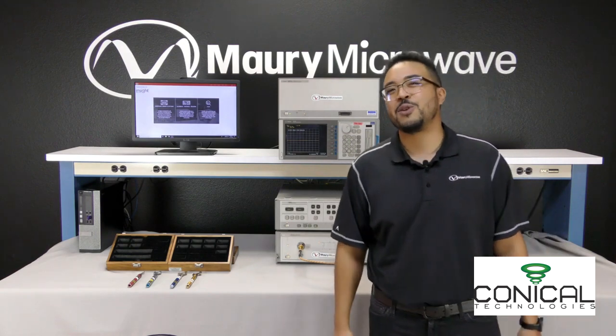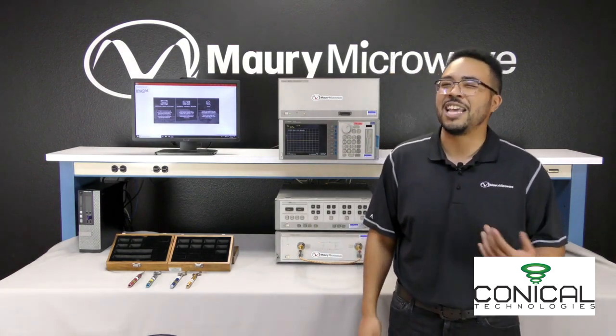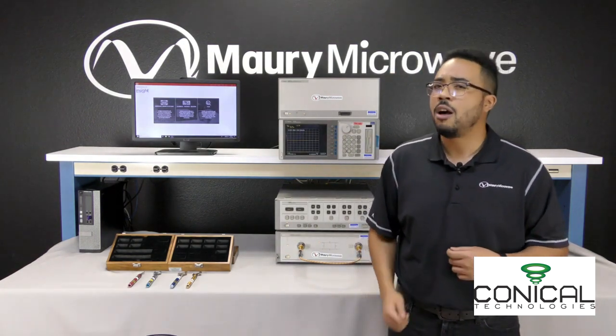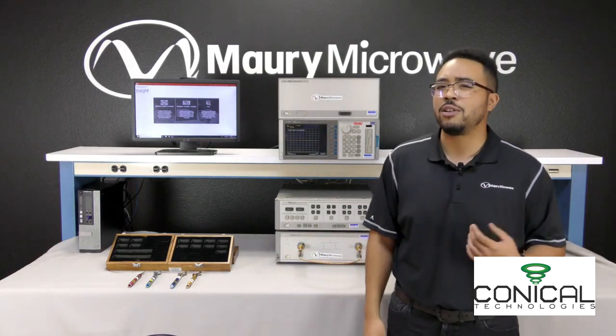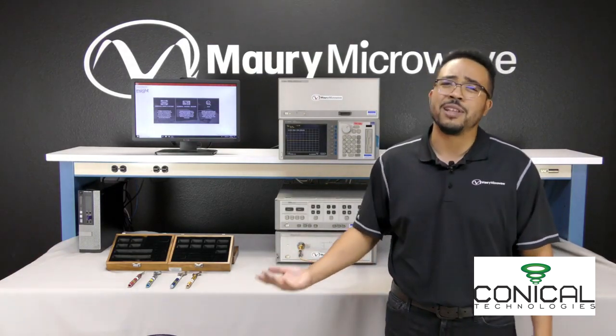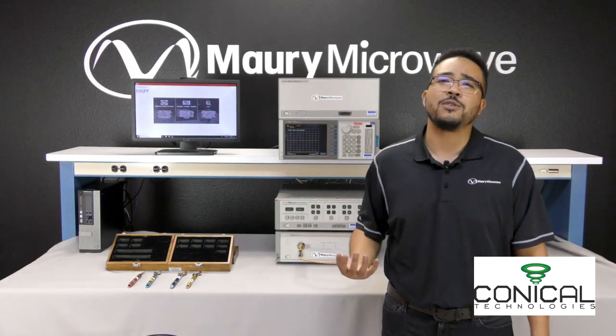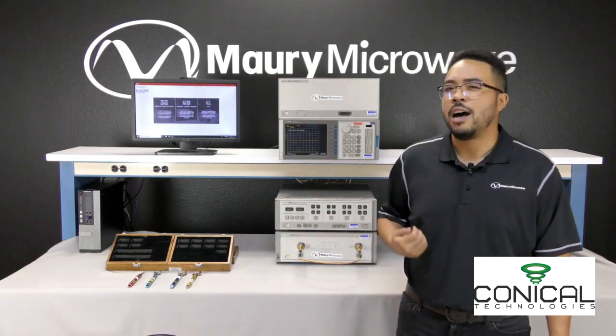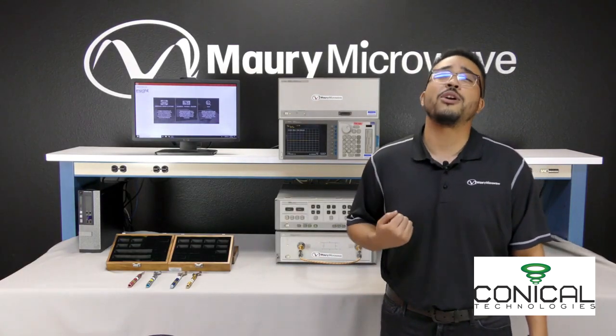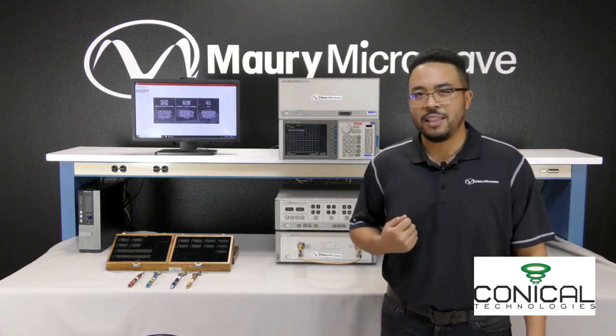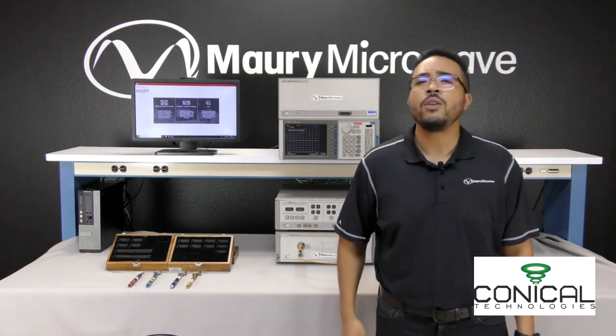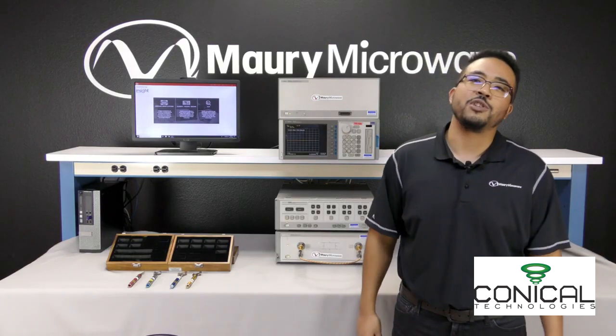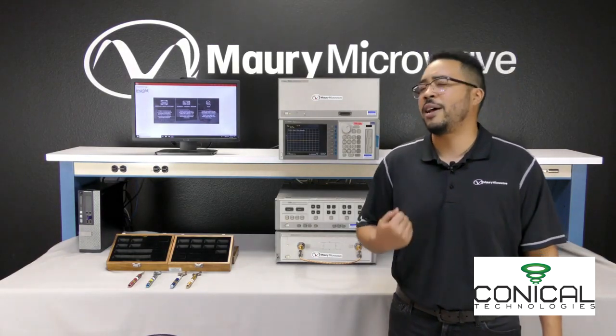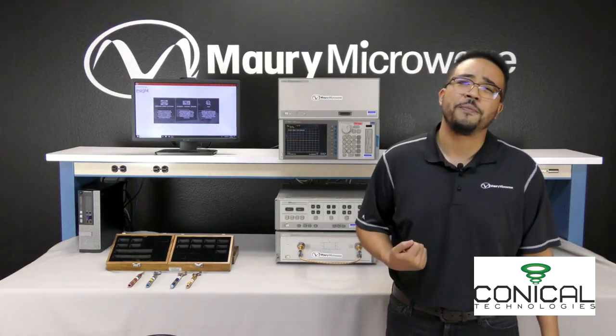Being 35-plus years old, these units may show age such as damaged or non-functional hard keys, obsolete cartridges and diskettes to load cal kits, dead or damaged displays, lack of a modern interface, which can be kind of clunky to use, a lack of compatibility with modern calibration techniques, and finally, lacks the paradigm of uncertainty. Ultimately, it'd be a shame to stop using such an incredible instrument because of cosmetic deficiencies or outdated software.